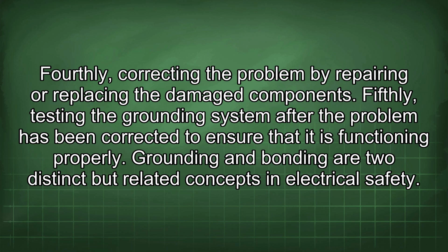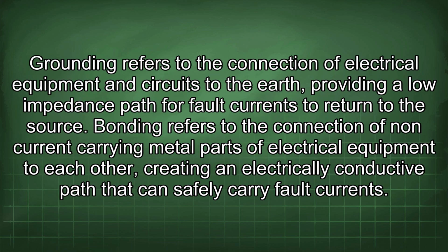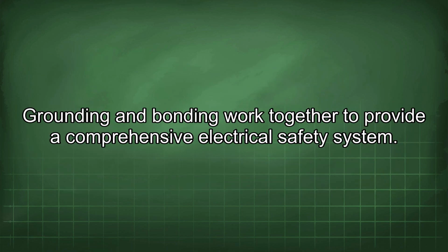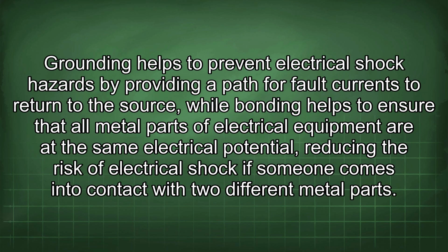Grounding and bonding are two distinct but related concepts in electrical safety. Grounding refers to the connection of electrical equipment and circuits to the earth, providing a low impedance path for fault currents to return to the source. Bonding refers to the connection of non-current carrying metal parts of electrical equipment to each other, creating an electrically conductive path that can safely carry fault currents. Grounding and bonding work together to provide a comprehensive electrical safety system. Grounding helps to prevent electrical shock hazards by providing a path for fault currents to return to the source, while bonding helps to ensure that all metal parts of electrical equipment are at the same electrical potential, reducing the risk of electrical shock if someone comes into contact with two different metal parts.